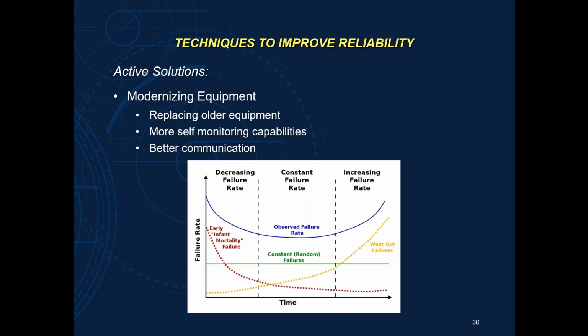Modernizing equipment is important. This is our typical, what they call a bathtub curve. The observed failure rate is comprised of 3 components. You have your infant mortality, you have your wear out failures, that's just common aging, and then you have constant random failures, things that just go wrong. All together, that puts a failure rate that forms a bathtub. When you do your calculation, if you're calculating based off of old equipment, you should be considering this and using aged failure rates. So replacing older equipment will put us in the better part of that curve.